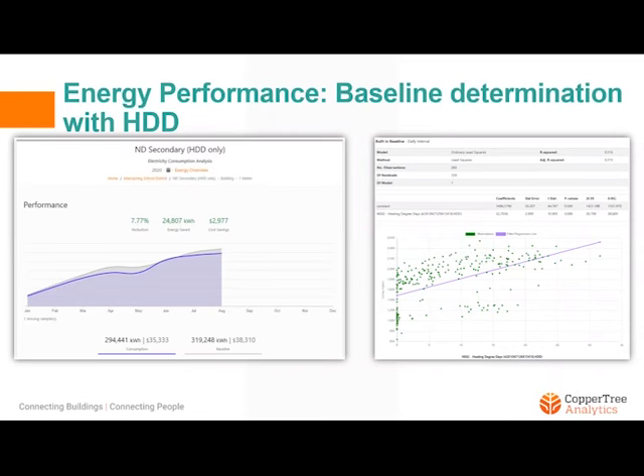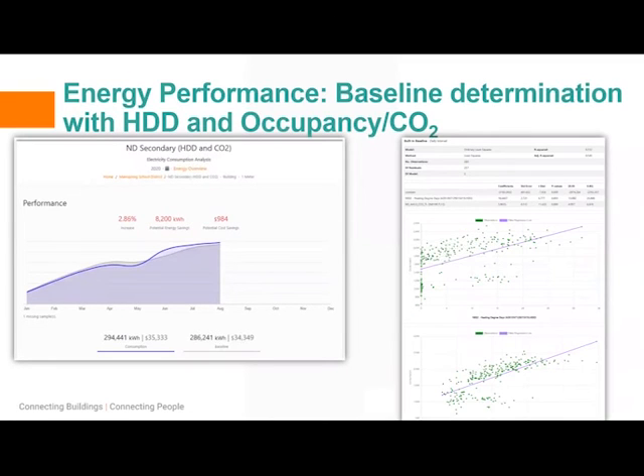But is that the full picture? Let's take a deeper look. We then realized that the occupancy of the building was changing throughout last year because of COVID-19. And we added another independent variable to the analysis to determine the actual baseline. When we did that, we included carbon dioxide concentration, which is an implicit occupancy sensor data. If you have actual occupancy sensors in the building, great, you can use that. That's explicit occupancy sensor information. But if you don't have that sensor availability, you can use something like carbon dioxide concentration, which is a reflection of actual occupancy in the space.